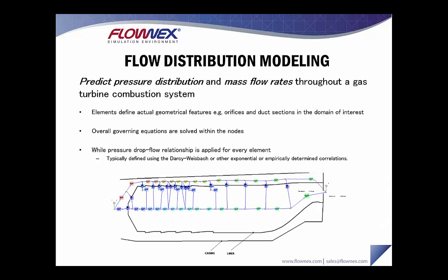Flow distribution modeling allows you to predict the distribution and mass flow rates through the gas turbine combustion system. Typically, elements define actual geometrical features such as orifices and duct sections in the domain of interest. The overall governing equations are solved within nodes, and a pressure drop–flow relationship is applied for every element, typically defined using the Darcy-Weisbach, exponential, or empirically determined pressure loss correlations.